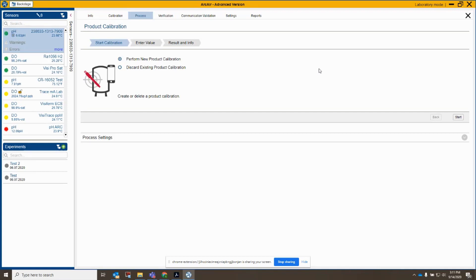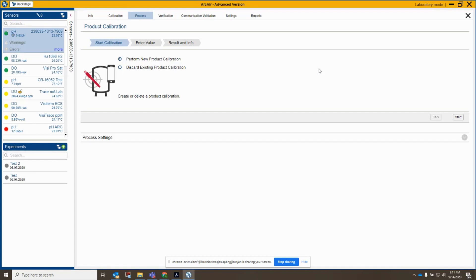And now I've built a little bit of offset into my sensor because I did that process calibration. And this is because I'm not using good laboratory practices. I'm moving the sensor back and forth, not waiting the full timeframe here. So I've completed a product calibration. The other thing that you notice here is that it didn't have the option to generate a report because this product calibration is assuming that this is being compared against my process liquid, the pH of my process liquid, and not against a standard buffer like 4 or 7 or 10 pH buffer. So that's why there's no report because it's not a formal calibration there.